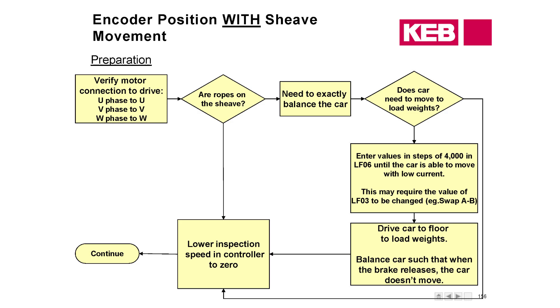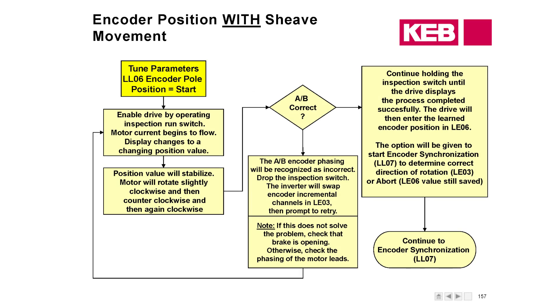One nice thing about the pole learn is that it automatically calculates the correct AB channel phasing for you — you don't have to manually select it or run to check if you're on the correct channel. The pole learn automatically does that, and it will tell you if you're on the wrong channel and make the change by itself, but it's up to you to do another SPI. Anytime you switch from a non-inverted channel to an AB-swapped setting, you need to do another SPI, because the position values are different for each channel.